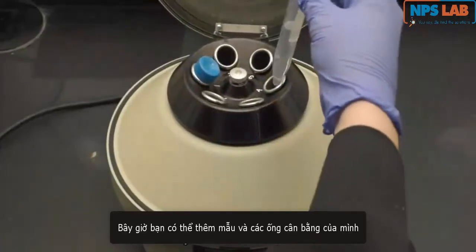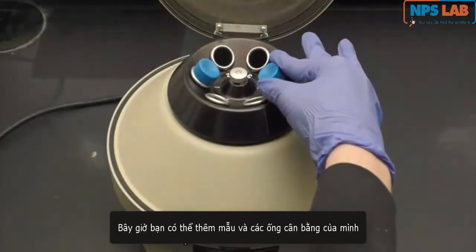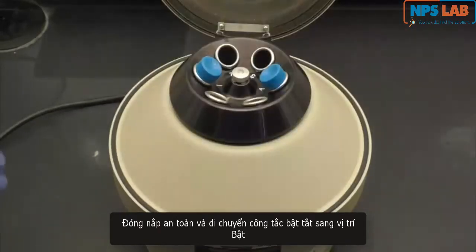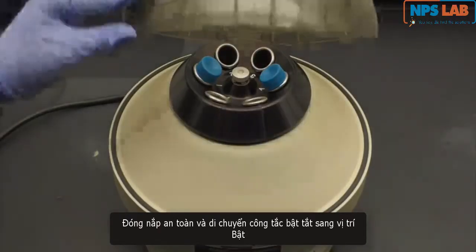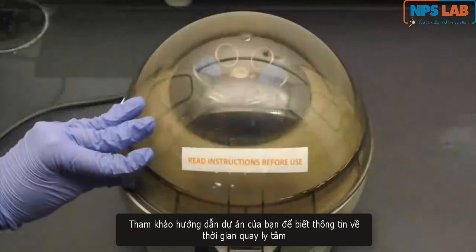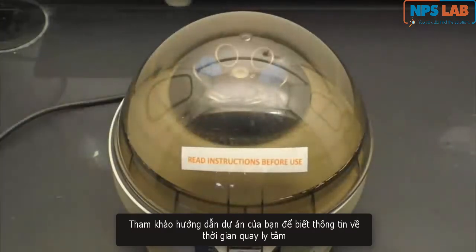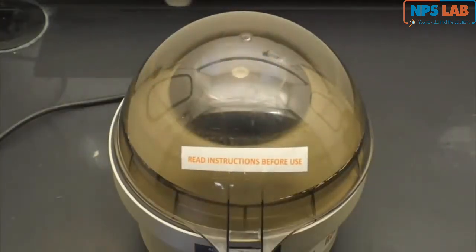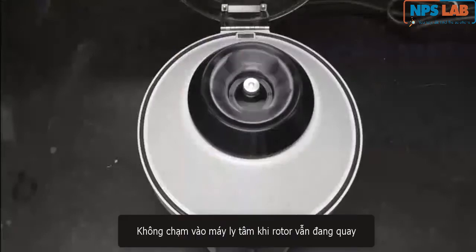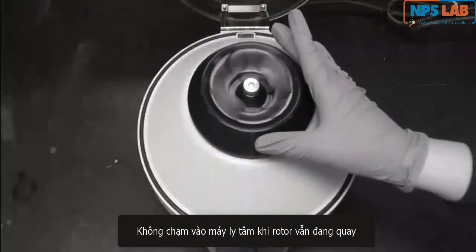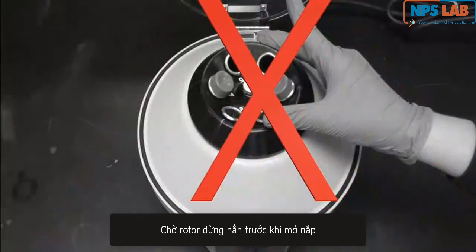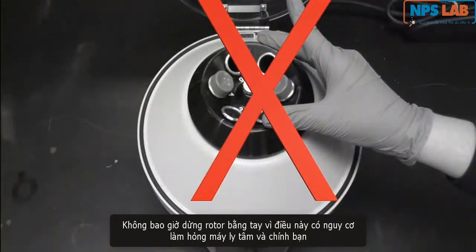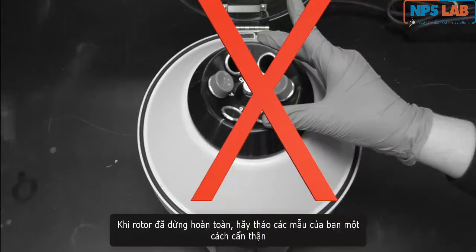Now you can add your sample and your balance tubes to the rotor. Shut the safety cover and move the toggle switch into the on position. Consult your project guide for more information on how long your sample should stay in the centrifuge. Do not touch the centrifuge while the rotor is still spinning. Wait for the rotor to come to a full stop before opening the lid. Never stop the rotor manually, as this risks damaging the centrifuge and yourself.